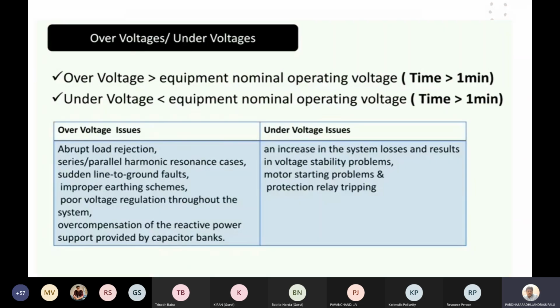In this context, we have over voltage and under voltage. Power quality problems and their characteristics are always discussed with respect to time, which means how long they occur, whether 10 seconds, 1 minute or 2 minutes. Over voltage is when the voltage is more than the equipment nominal operating voltage for more than 1 minute. Whereas under voltage is when the voltage is less than the equipment nominal operating voltage.